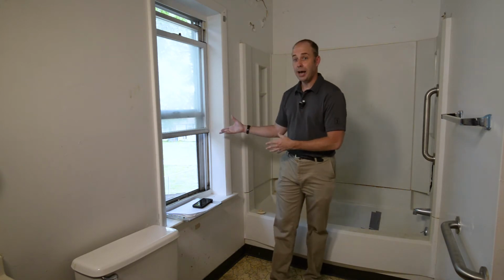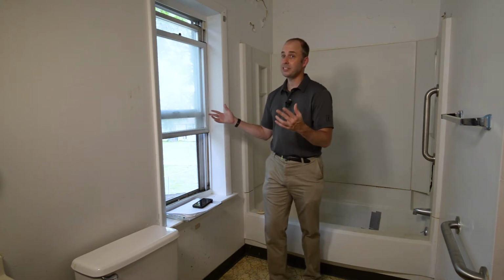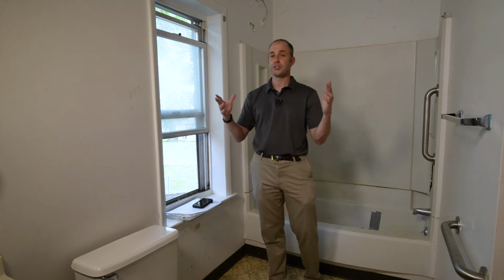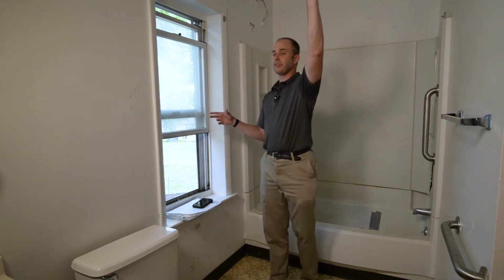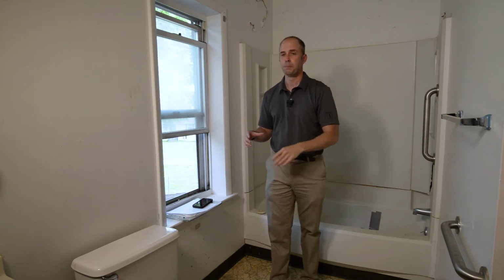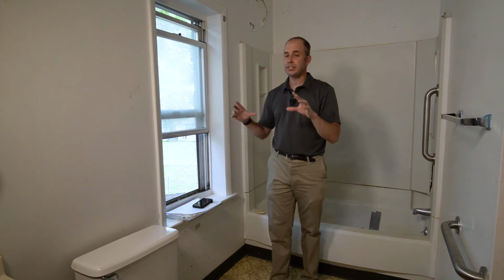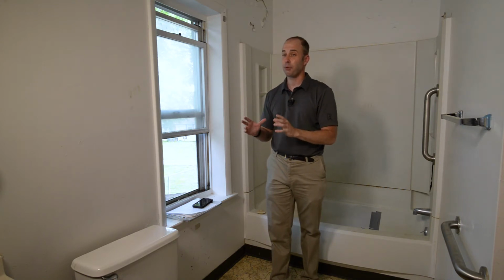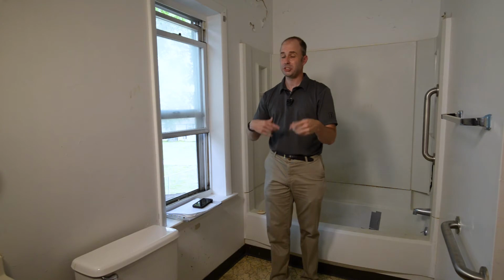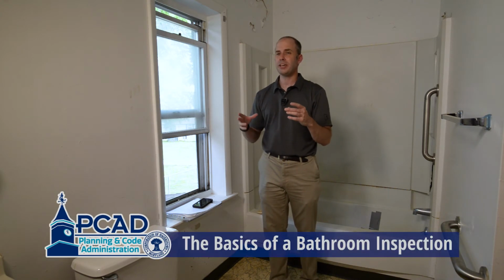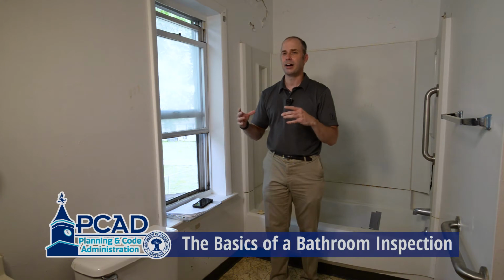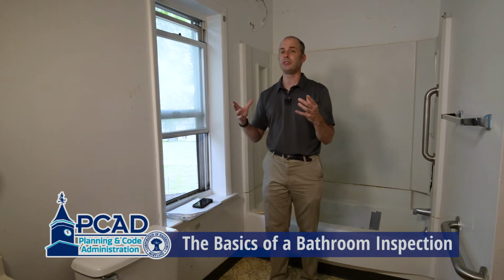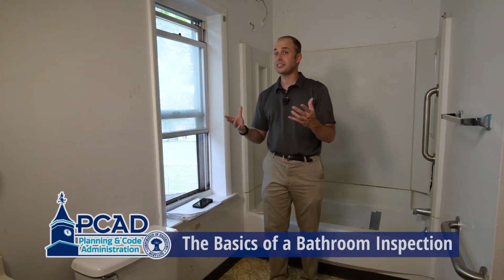Now, let's say you don't have a window in your bathroom. Well, it still needs to ventilate. So you need to have an exhaust fan. It's probably off camera here, but we have an exhaust fan in this bathroom. And it needs to at least move 50 cubic feet per minute. So that means how much changeover air in the bathroom every minute. And 50 cubic feet may sound like a lot, or it might sound like a heavy duty type of ventilation fan, but it's not.